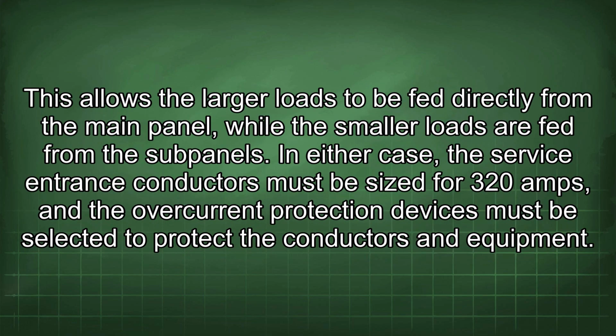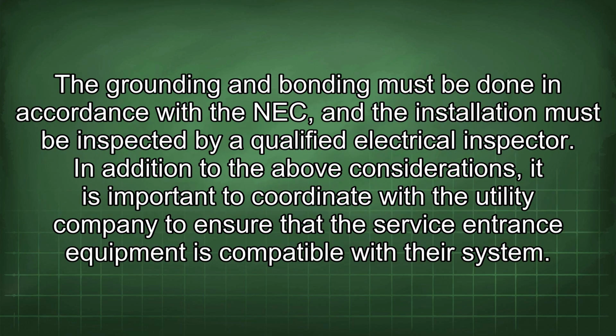If the load is heavily concentrated in one unit, a single 320 amp panel with subpanels may be more appropriate. This allows the larger loads to be fed directly from the main panel, while the smaller loads are fed from the subpanels. In either case, the service entrance conductors must be sized for 320 amps, and the overcurrent protection devices must be selected to protect the conductors and equipment. The grounding and bonding must be done in accordance with the NEC, and the installation must be inspected by a qualified electrical inspector.